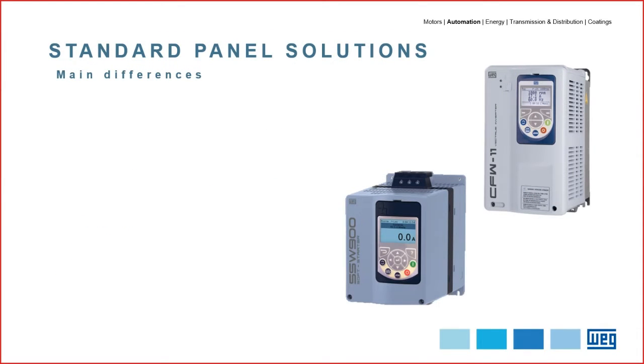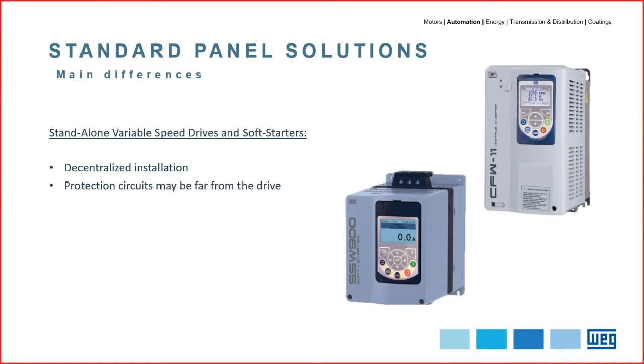To answer this question, we should take into consideration the main differences between a standalone and a panel solution. We can say that the standalone VSD and soft starter are ideal for decentralized installation, like close to the machines and/or at the wall. These products may also be considered for application when the required individual protection does not need to be installed close to them. Also, when an additional filter or electrical equipment is not part of the solution. And of course, a standalone is also a solution when the protection degree requirements are less restrictive.